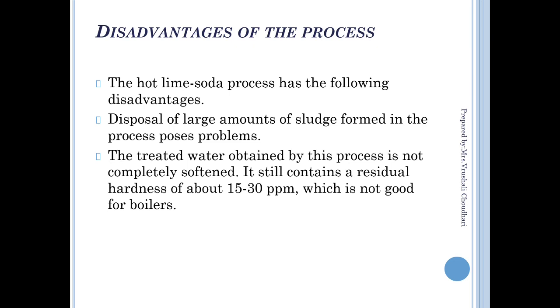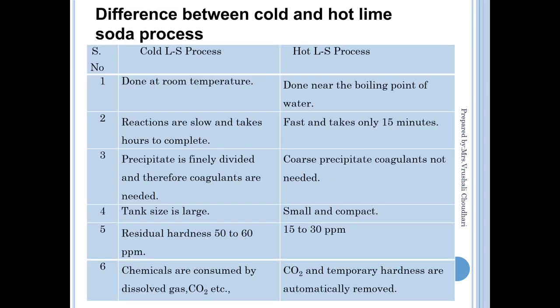Disadvantages of the hot lime-soda process: it produces a large amount of sludge which clogs the pores of the filter. The treated water is not completely softened — about 15 to 30 ppm of hardness still remains, which is not suitable for boiler use.